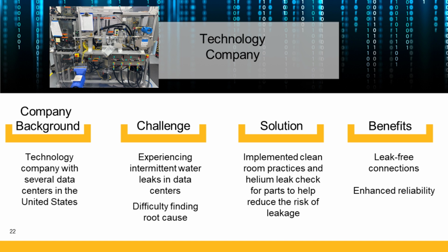The second example is a technology company that had several data centers in the United States. They were already using liquid cooling but experienced intermittent leaks, and had difficulties finding the root cause. So they called Parker to support, and inspection of the quick disconnect couplings determined small amounts of debris were causing leakage.